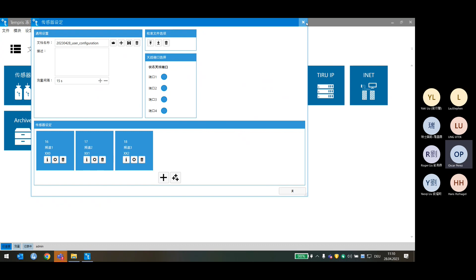We have automation settings for integration with the SCADA system: IP addresses, type of communication, activate or not, and we can test the communication with the IP address on the other side for the different channels. When we have automation, we can also see during measurement the output in milliamperes for the signal, in case we configure 4-20 range.